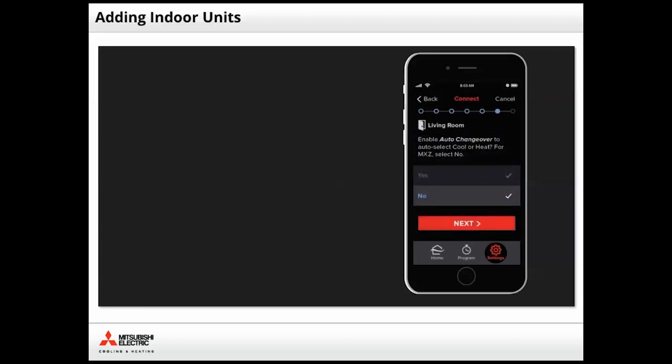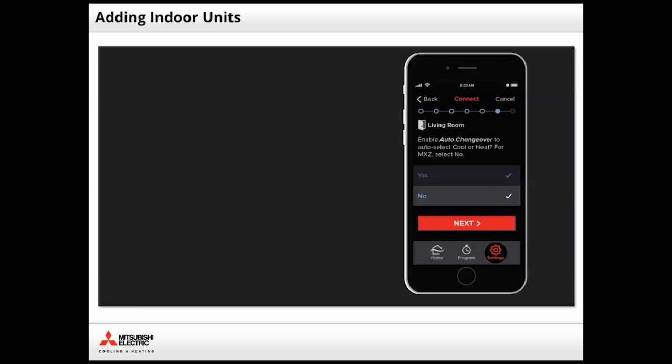Selections for Auto Changeover can be made by tapping the corresponding row. Keep the default No option if the system is a multi-zone MXZ to avoid unexpected periods in standby mode. In this instance, we'll keep the default response and simply tap Next.